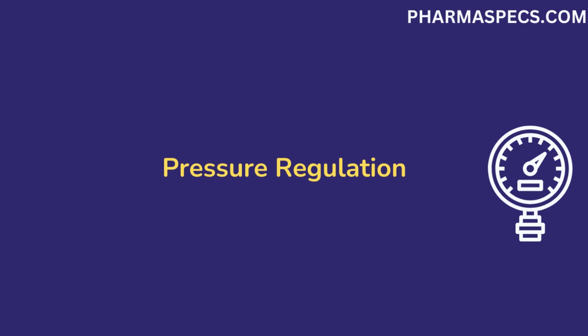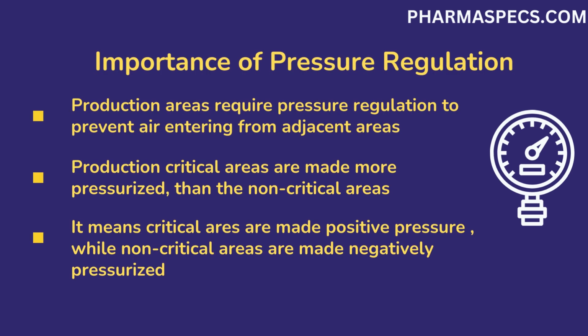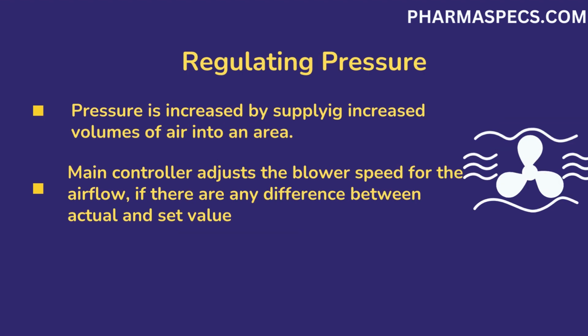Pressure regulation. The final variable which is controlled through pharma HVAC is the pressure. Its main purpose is to increase or decrease the pressure of an area as compared to adjacent or surrounding rooms or areas. The main purpose of pressure regulation is to prevent air leakages into the area. Air leakage into the area is the root cause of various pharma related problems such as contamination and temperature irregularities. Production critical areas are made more pressurized than non critical areas. It means critical areas have positive pressure profiles, while non-critical areas have negative pressure profiles.